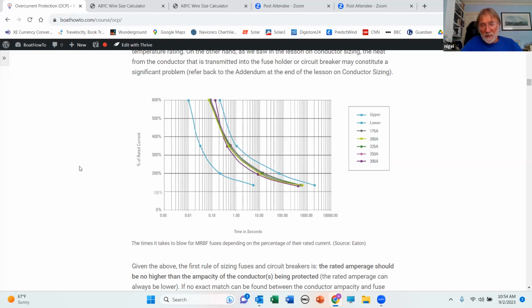Because we're not required to have a fuse, we don't have to base the fuse on the ampacity of the conductor. We can basically put in whatever we want. So for a typical 100 horsepower sailboat auxiliary engine, I'll put a 300 amp slow blow fuse in that circuit, and it's never going to blow under cranking currents. But in the event that we get a short circuit in the starter motor or in that circuit, the fuse will blow and protect the boat. So I do actually always fuse those circuits.